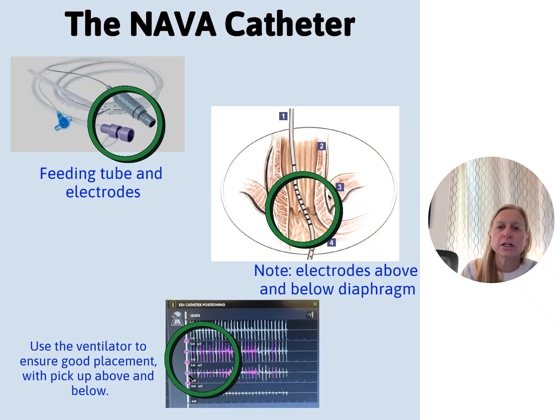In the second picture here, you see the electrodes. This is from the company. This is a typical picture. You want some above and some below the diaphragm. So that's what you see here. That's what all these little dots are that are going on within here. You've got this in perfect placement. Then you've got your EDI positioning on your ventilator. It's a screen. You get to click on it and it helps you see what's going on there. So use the ventilator to help ensure good placement.